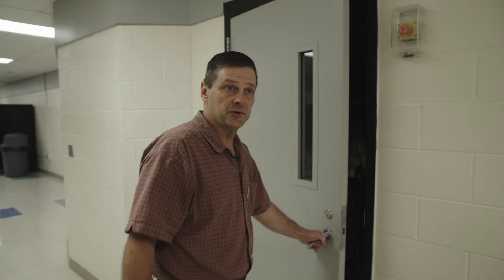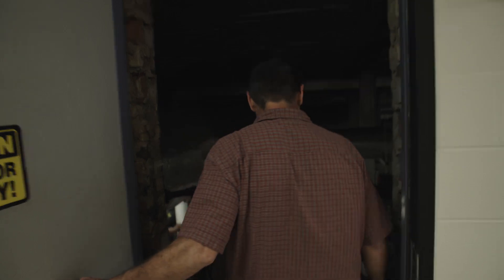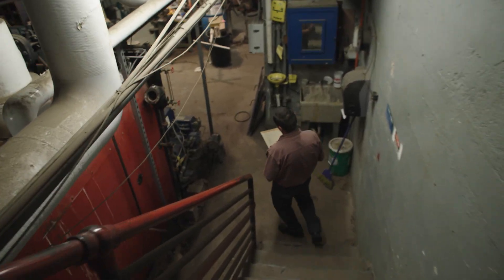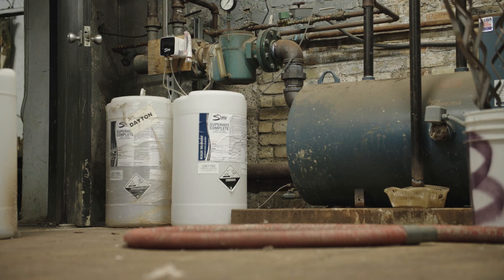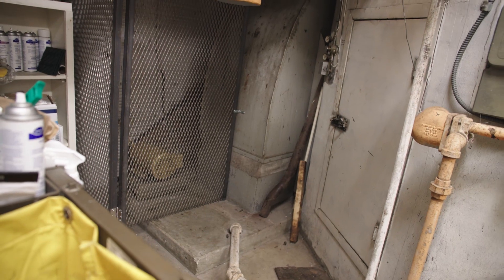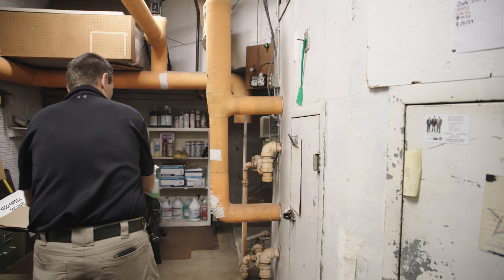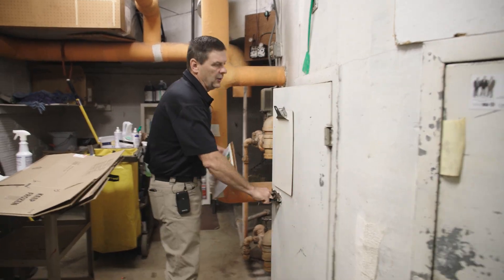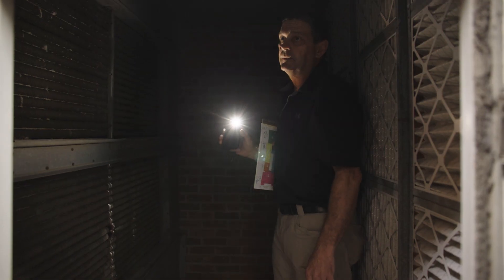I'm having to run units that are 50, 60, 70 years old. We'll go down to the boiler room. The condensate tank here is quite small. This unit is original to 1954 — it supplies the air for the K-4 wing. We have overextended the shaft on this unit with the bearings. It's kind of a band-aid on here to get us by.